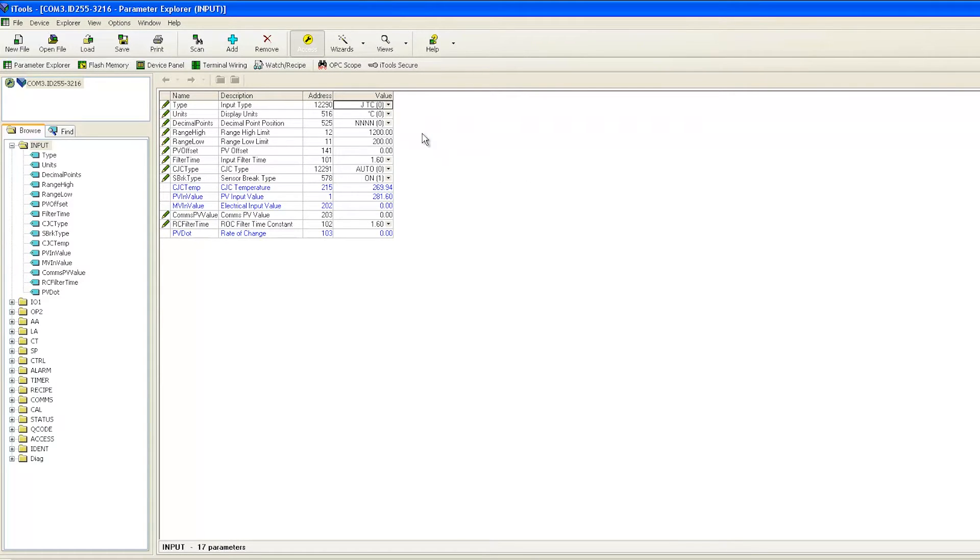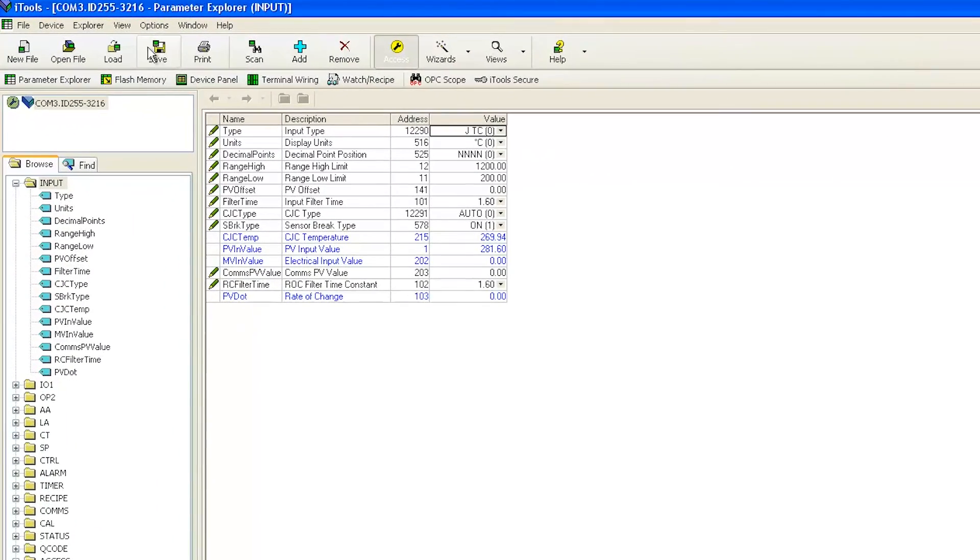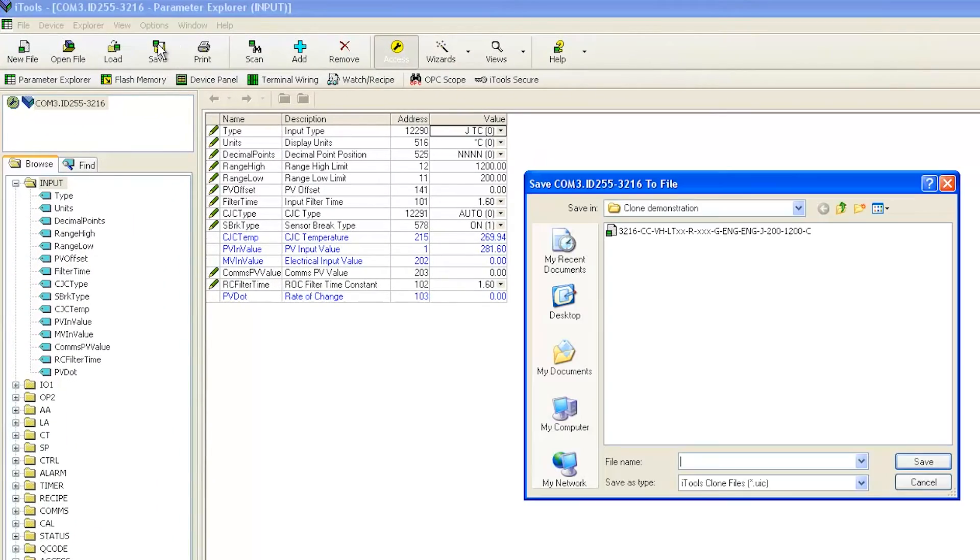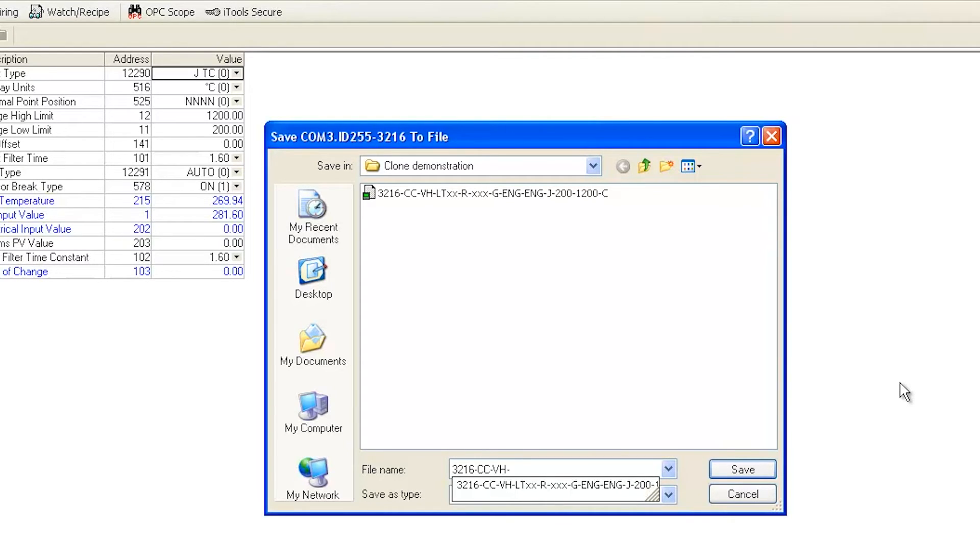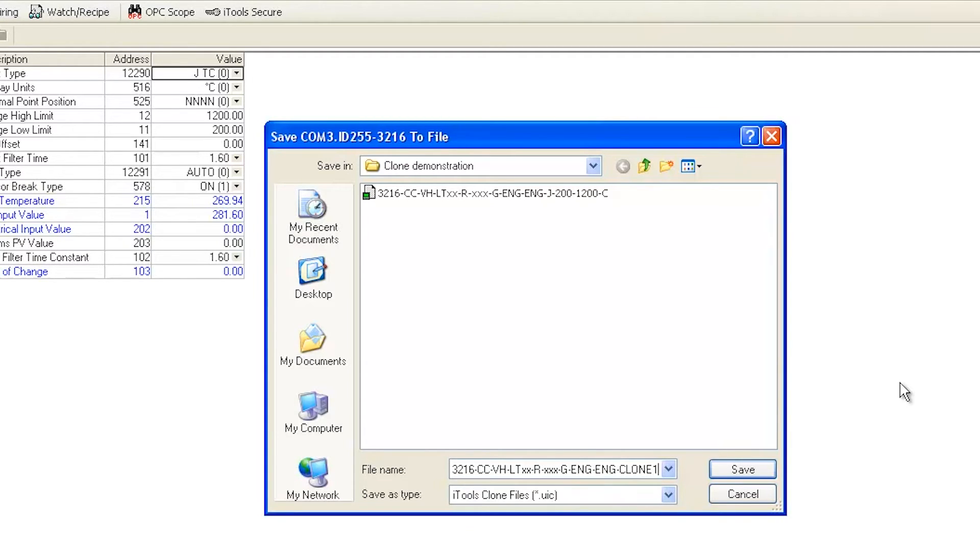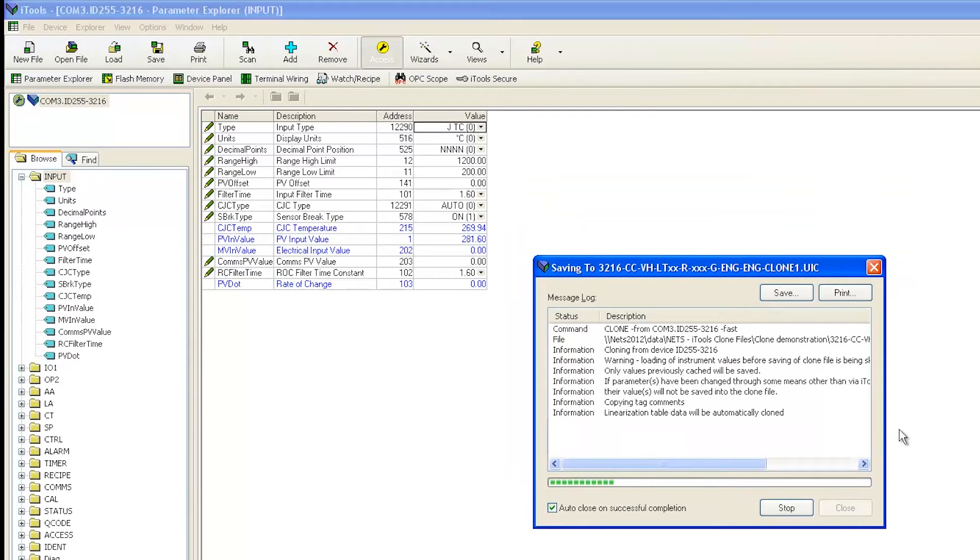In order to clone the controller, go to the toolbar at the top and press the Save icon. Navigate to the appropriate directory on your computer where you would like to store the file, give it an appropriate name, and ensure that the save type is .UIC. Then click Save. You now have a clone file with all the configuration settings of the controller.